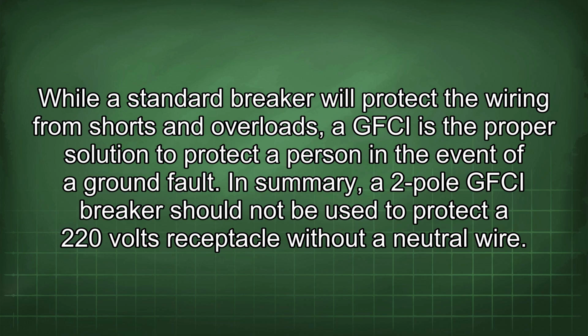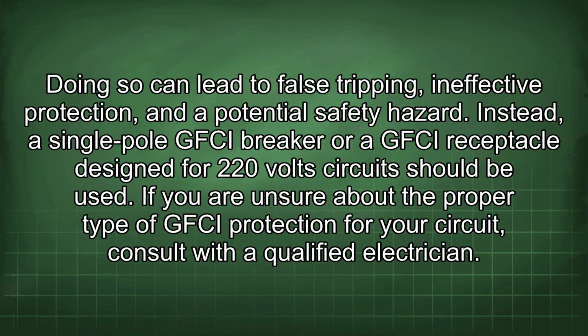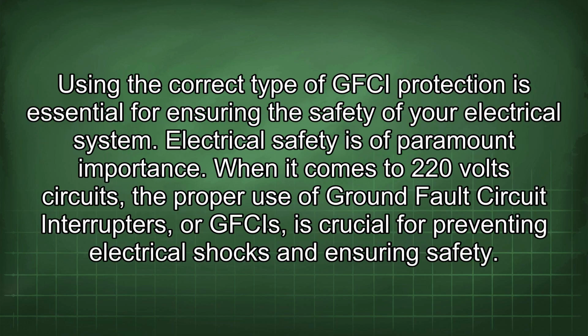In summary, a two-pole GFCI breaker should not be used to protect a 220 volts receptacle without a neutral wire. Doing so can lead to false tripping, ineffective protection, and a potential safety hazard. Instead, a single-pole GFCI breaker or a GFCI receptacle designed for 220 volt circuit should be used. If you are unsure about the proper type of GFCI protection for your circuit, consult with a qualified electrician. Using the correct type of GFCI protection is essential for ensuring the safety of your electrical system.